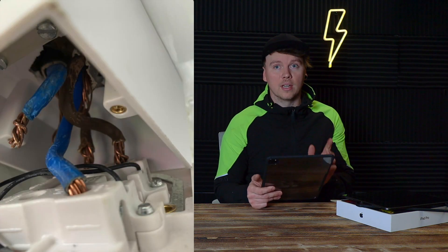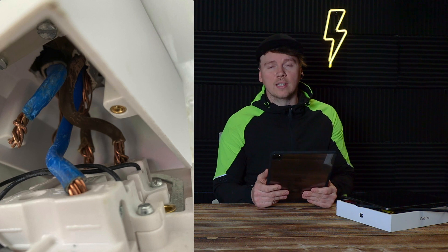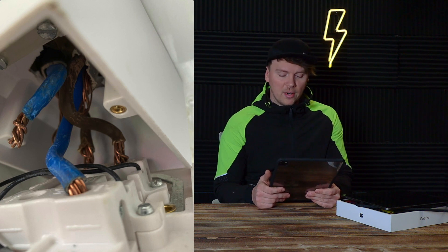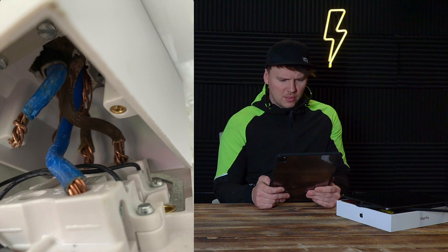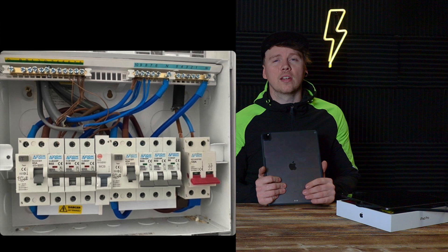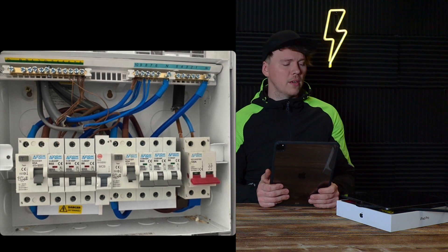Next one is from Cablesmith Electric. We see this all the time — Adam and I do this all the time: doing an EICR, pull the shower pull cord down, because most of the time the cables aren't in the connections properly, they're not tightened off, and you get a lot of thermal damage on the pull cord itself. On this one it's been mashed up — the pull cord's been pulled down, cables have been twisted and jammed in, just not very good. And I can't quite see where the earth or CPC is connected. Then the next one — a fuse board recently done that has no sleeving on the earth and also no main earth into the board. Bit of a no-no.